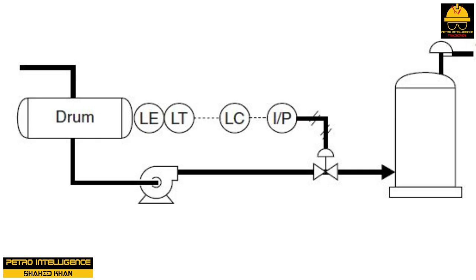A typical level control system uses a primary element sensing device, a direct or indirect level transmitter, controller, transducer, and control valve. Level control loops use floats, displacers, or differential pressure transmitters. A DP cell detects level changes; the primary element or sensor is inside the transmitter. These two devices couple to detect and send a signal to a level controller. A transducer converts the signal and opens or closes the control valve.